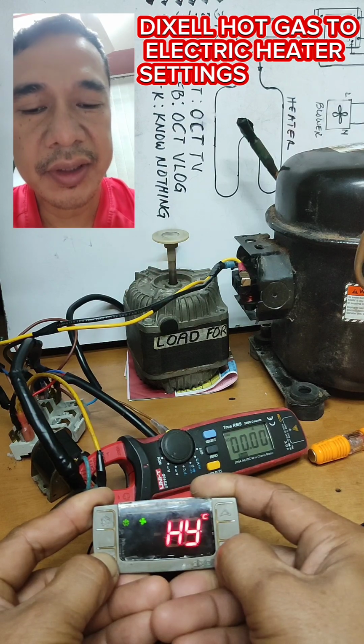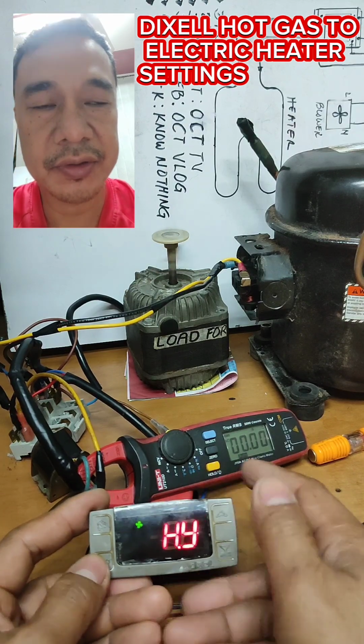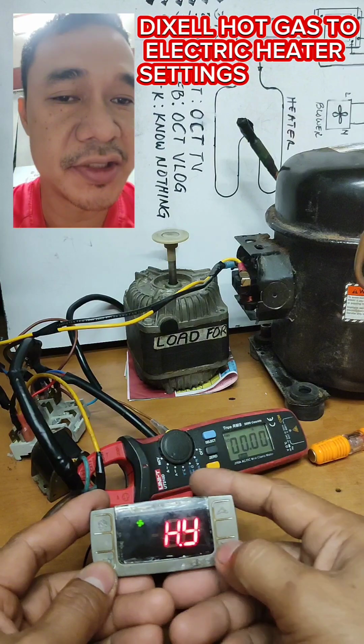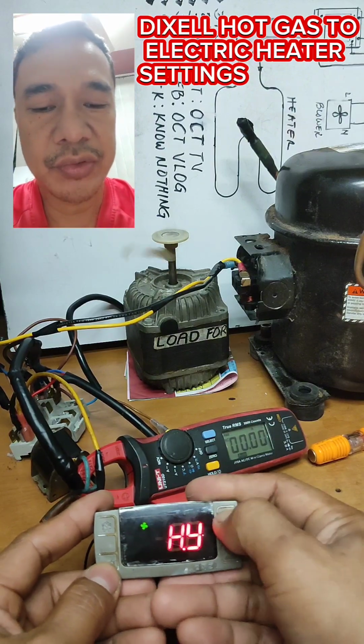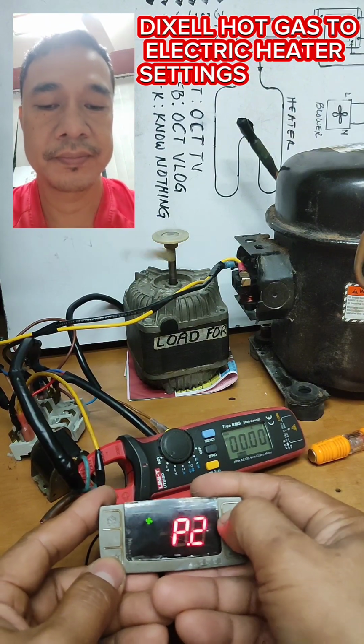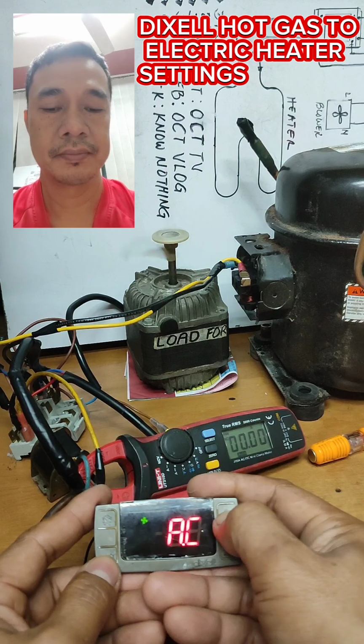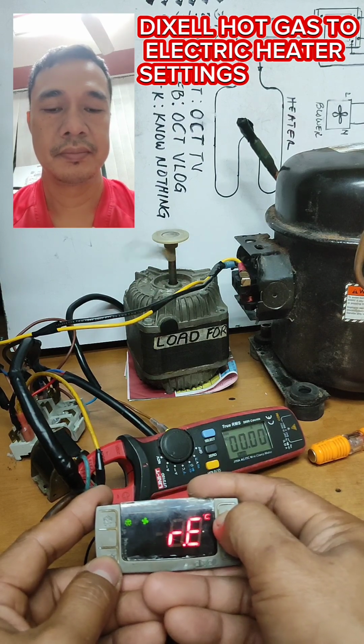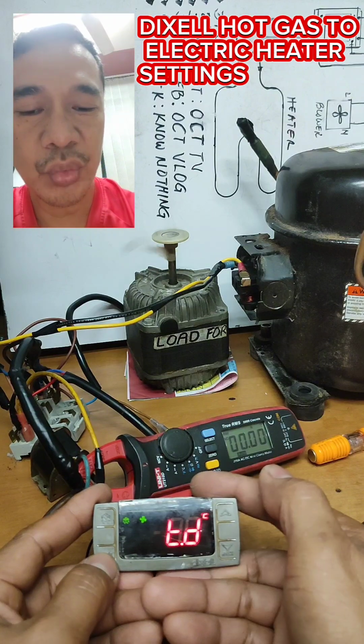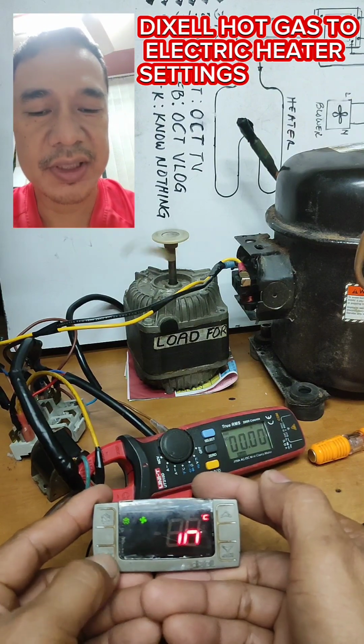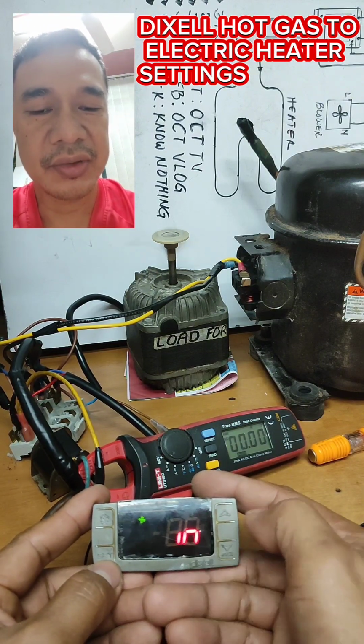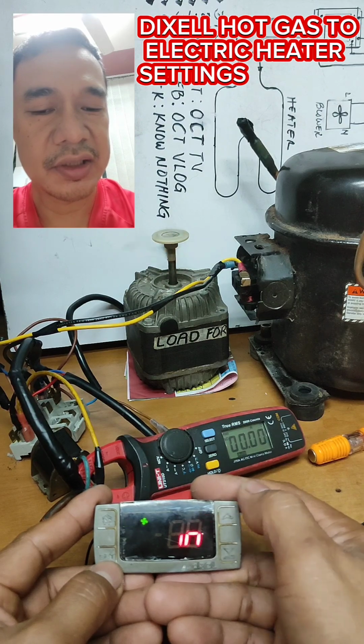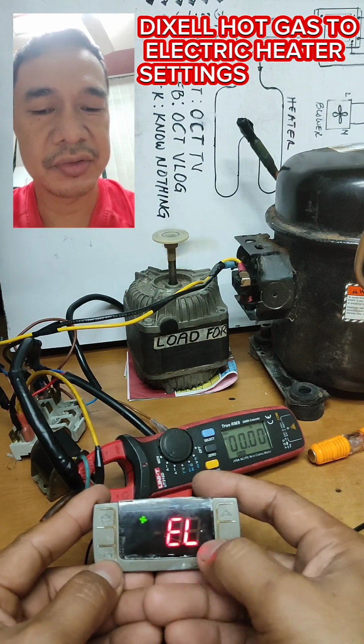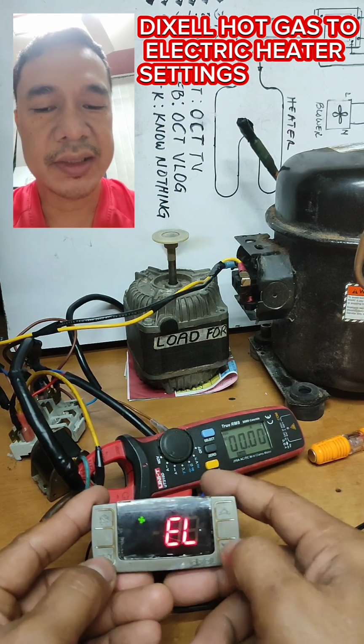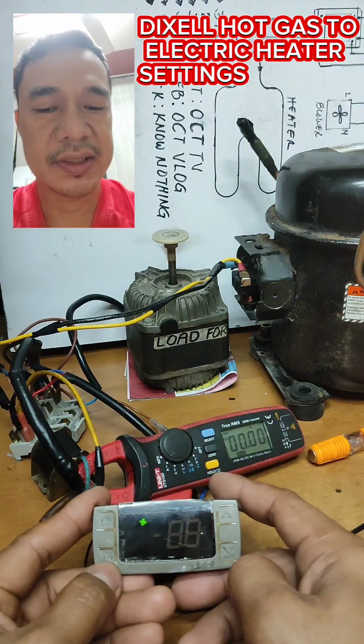And here are the parameters you need to change. Let's browse for TD, which is the type of defrost. Preset from hot gas defrosting, we're going to replace with electrical heater preset.